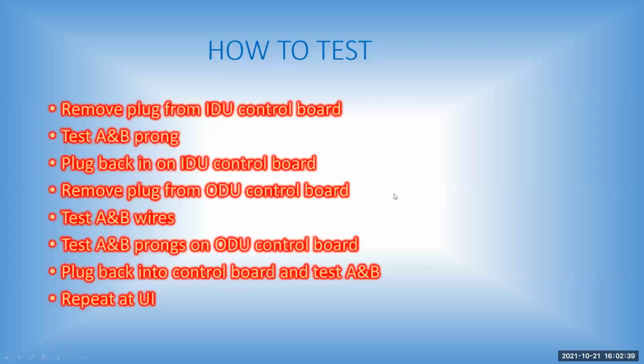Go over to the next slide here, how to test. First thing you want to do anytime you're getting these errors, and I should put it on here, shut your system completely down, do a reboot. You can even do a reinstall on your thermostat. About 80% of the time that fixes your problem. If that's done and your problem's not repaired, we're moving forward with these following steps.